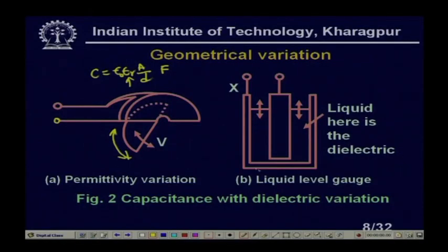Another example is a liquid level gauge. It is cylindrical in shape with an inner rod and an outer cylinder acting as the two plates. When liquid is poured in, the dielectric medium between the plates consists of two different materials: air and liquid. As the tank fills, there is more liquid and less air between the plates, so the dielectric medium changes, changing the capacitance. This can measure the level of liquids and also solids in powder or granular form.